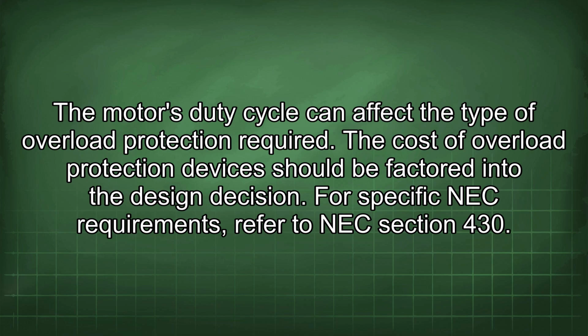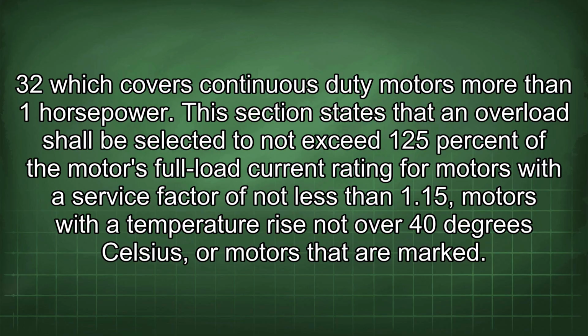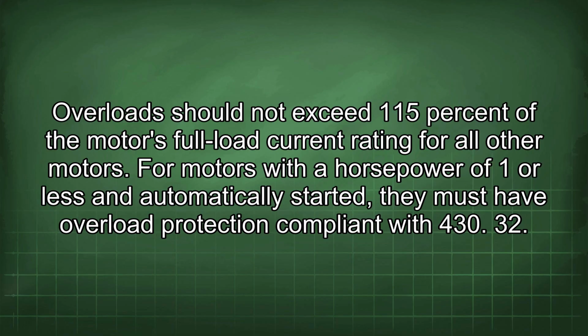For specific NEC requirements, refer to NEC Section 430.32, which covers continuous duty motors of more than 1 horsepower. This section states that an overload shall be selected to not exceed 125% of the motor's full load current rating for motors with a service factor of not less than 1.15, motors with a temperature rise not over 40 degrees Celsius, or motors that are marked accordingly. Overload should not exceed 115% of the motor's full load current rating for all other motors.